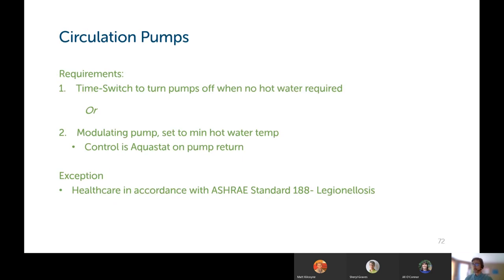Circulation pumps on hot water systems. They need to have either a time switch that turns the pumps off when there's no hot water required in the building, or have modulating pumps that are set to minimum hot water temperature controlled via an aquastat on the pump return. An exception to that is healthcare facilities, where Legionella, in accordance with ASHRAE Standard 188, could be a problem with turning down the pump speed circulating throughout the building.